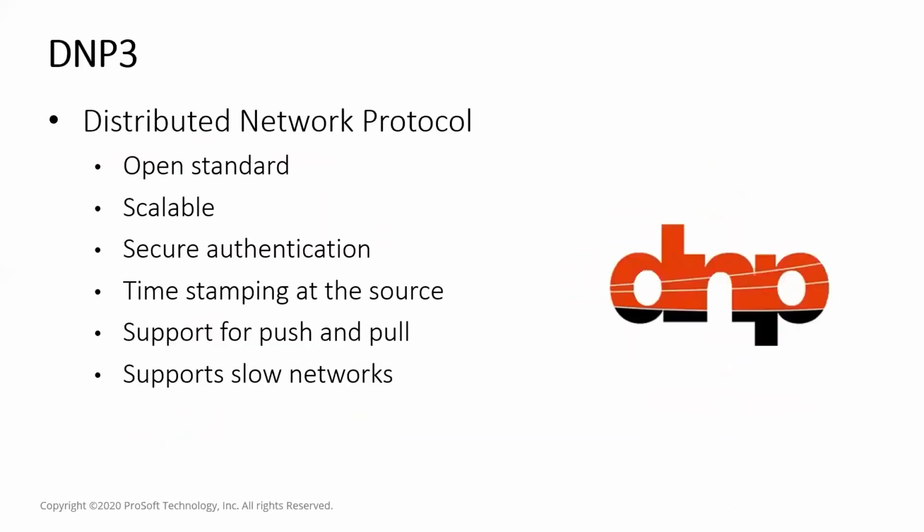So the solution is actually a protocol, and that protocol is DNP3, or Distributed Network Protocol. The solution from ProSoft uses this protocol to address the problems that we just looked at. The reason DNP3 works as a solution is because of some of those features that I've listed. One of the biggest advantages of this protocol is that it's highly scalable. You could have thousands of devices on a single network.